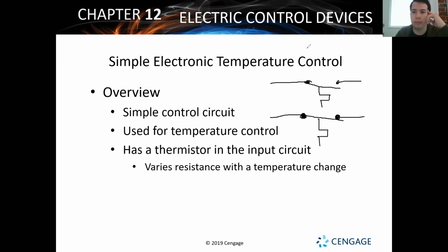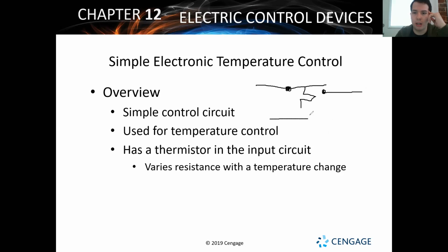For a furnace, you're going to see it where it's going to be a temperature switch again - normally open, but it'll be close on a fall. So a heating thermostat will close on a fall in temperature. If the room starts getting colder, that's a fall in temperature - that would make sense, turn the heat on as it gets colder. If the temperature rises in a room, turn the AC on. That makes sense, so close on a rise is for your cooling, close on a fall is for your heating. That's the easy way to think about those two.